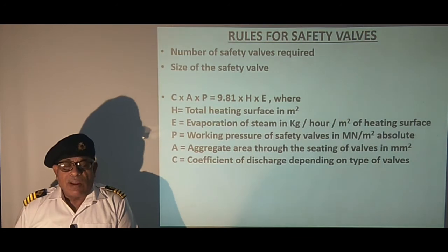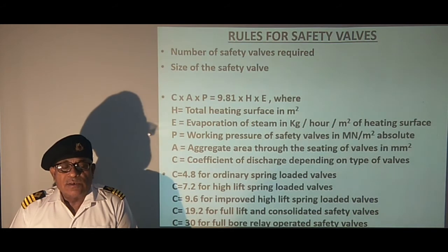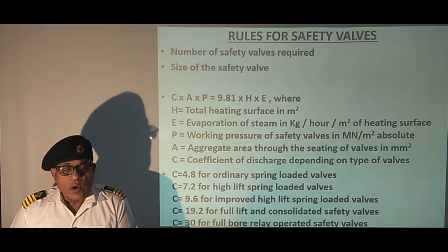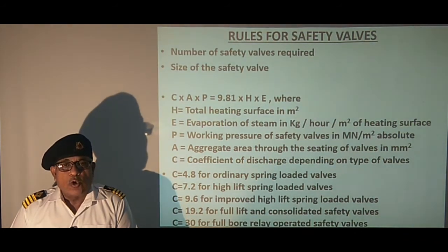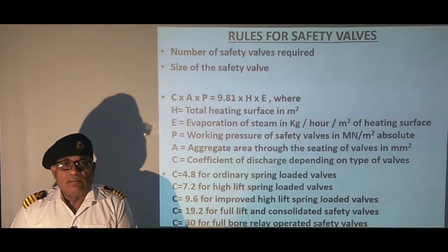We have studied several valves and the coefficient of discharge is given as below. The value of C is 4.8 for ordinary spring-loaded safety valves, 7.2 for high lift spring-loaded valves, 9.6 for improved high lift spring-loaded valves, 19.2 for full lift and consolidated safety valves, and 30 for full bore relay operated safety valves.